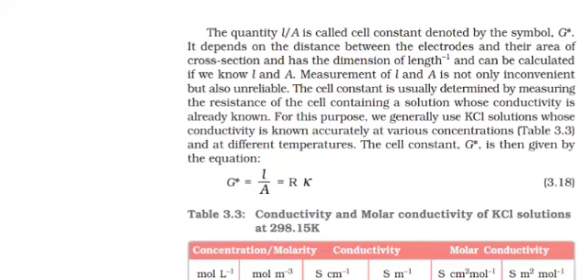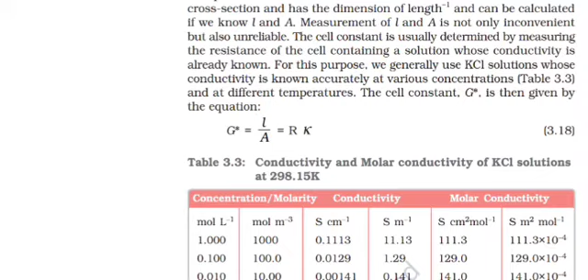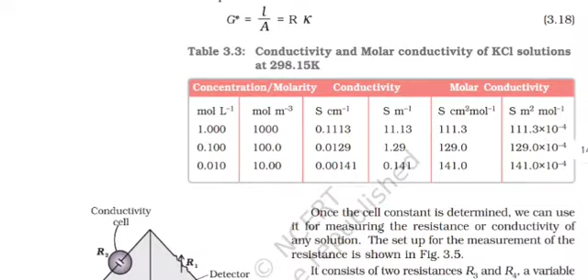The cell constant is usually determined by measuring the resistance of the cell containing a solution whose conductivity is already known. For this purpose, we generally use KCl solutions whose conductivity is known accurately at various concentrations and at different temperatures. The cell constant G star is then given by the equation G star equals L by A equals R into kappa. Once the cell constant is determined, we can use it for measuring the resistance or conductivity of any solution.